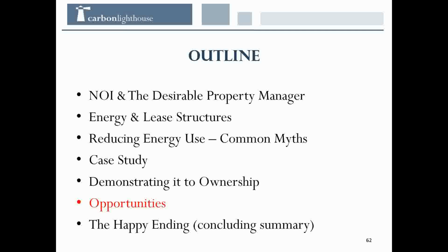If you can't do that because you don't have any one of those quite rigorous data streams that you need, you can measure individual systems you're changing. So we do this a lot, and particularly because building use changes, tenants and occupants can add data servers or remove them, so that obviously impacts the building use in a very large way. So we'll make predictions about individual circuits. So we'll predict what mixed air temperature should be, what flow rate in a pipe should be, what fan speed should be, what kW use an individual circuit should be, all sorts of things like that. And we make those predictions by the hour, so after a month we have literally a few thousand different data points of predictions we've made to reality to compare.